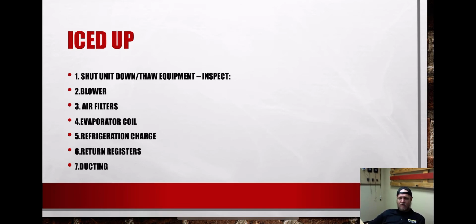Thawing the equipment kind of depends on what it is, right? If it's hot out, you can let the blower operate to kind of breathe some of that warm air in. Kind of pull some of that warm air in. If it's a gas pack, obviously you can run it in heat. That's not really going to help you if the heat exchanger is behind the coil. But I always like pulling the return or the supply panel open and letting some of that warm air just kind of go across that coil and blow it out onto the roof, and let that thing thaw out.